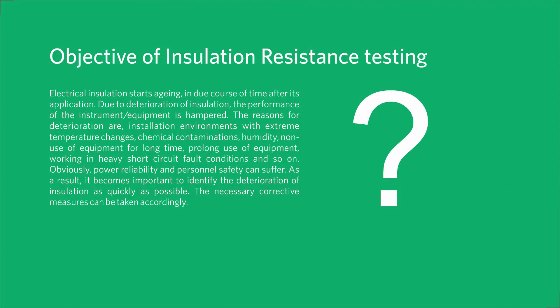Objective of insulation resistance testing: Electrical insulation starts aging in due course of time after its application. Due to deterioration of insulation, the performance of the instrument or equipment is hampered. The reasons for deterioration are installation environments with extreme temperature changes, chemical contaminations, humidity, non-use of equipment for long time, prolonged use of equipment, and working in heavy short circuit fault conditions. Power reliability and personnel safety can suffer, so it becomes important to identify the deterioration of insulation as quickly as possible, and the necessary corrective measures can be taken accordingly.